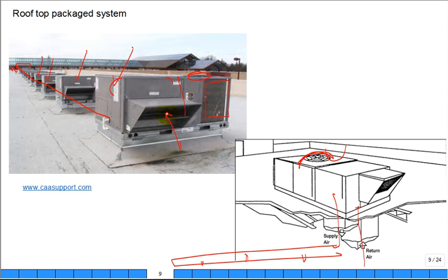But economizer is, let's say they're trying to keep the inside of the building cool, but this morning it was about 45 degrees when I was getting into my vehicle, I could just take the outdoor air as it is, draw it through a filter, and throw it into the building, and it would work perfect. And that's economizer mode. So when you see this little hood out here, that's typically what it's for. Taking in some outdoor air and could be completely running in economizer mode if it's set up that way.